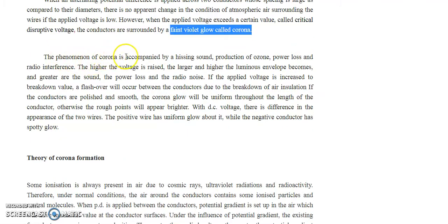The phenomenon of corona is accompanied by, first, a hissing noise. Hope some or most of you have noticed this while passing very close to a high voltage transmission line, and this hissing noise you can notice particularly in the rainy season. During the night you can easily hear this hissing sound. Production of ozone is another contribution, and power loss is another disadvantage of this corona, and radio interference. These four are the phenomena of corona.